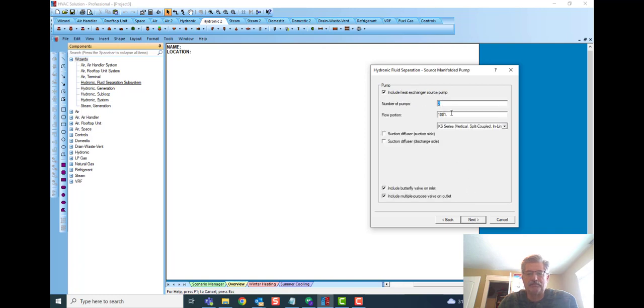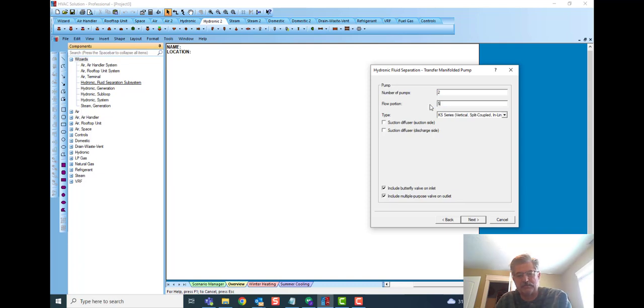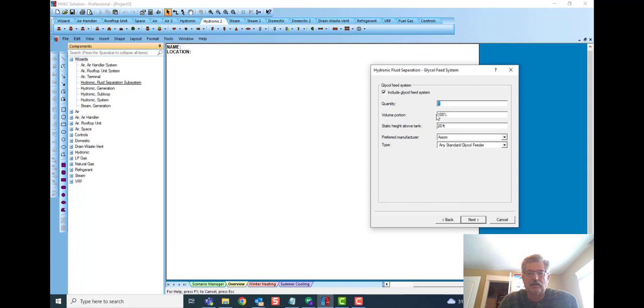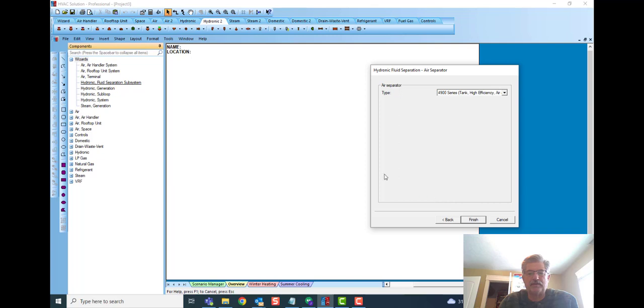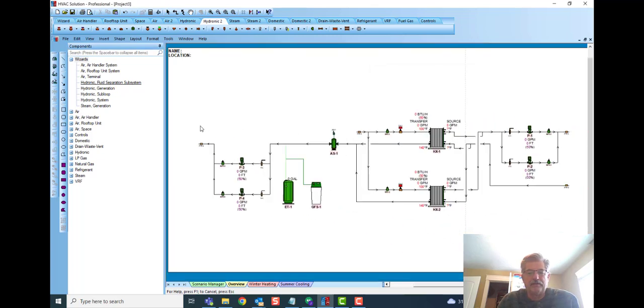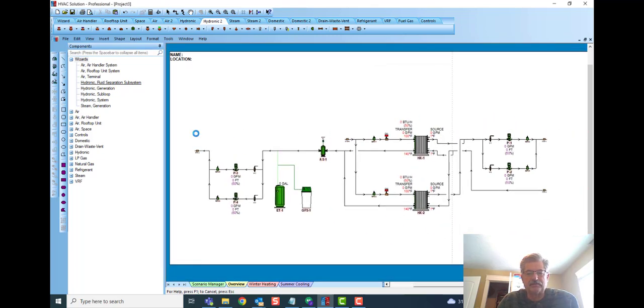Would like to do 2 pumps. We can do those at 50%, so we made the heat exchangers 50%. Same thing with the transfer pumps. We'll go with the Taco KS series. One glycol feed, we have Axiom in here, and you can see we have different choices of all the different feeder systems which they make. Then one expansion tank, one air separator. And there is my 2 heat exchangers with the related pumps.